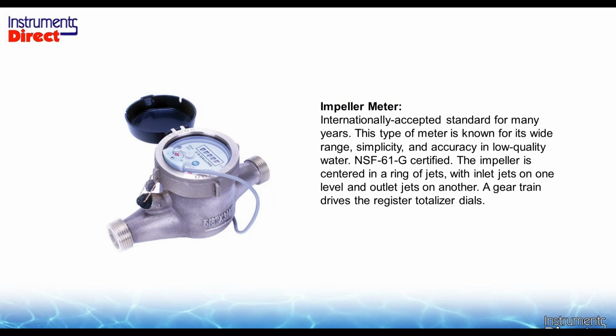Here's a typical example. This would be called an impeller meter. It looks like your traditional water meter, with a little sweep pan and the odometer. This uses an impeller that's gear attached to the display itself. So when it goes in, the wheel turns around and it makes the odometer monitor. So this is just a conventional method that's been around for a long time. The economics are relatively inexpensive, and of course their prices are based upon pipe size.